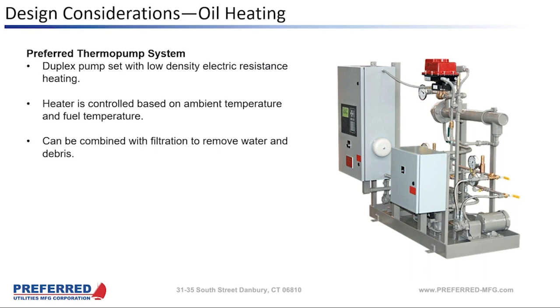And I think most of these systems had about 6 day tanks. So they would run through and pump cold oil out of the day tank one at a time, replace it with hot oil, and then throw a 3-way valve. And then we had an adjustable time where we could just circulate hot oil in and out of the main tank to put some hot oil in the main tank as well. And that system kept all the fuel warm throughout the whole system: main tanks, piping, day tanks, everything.